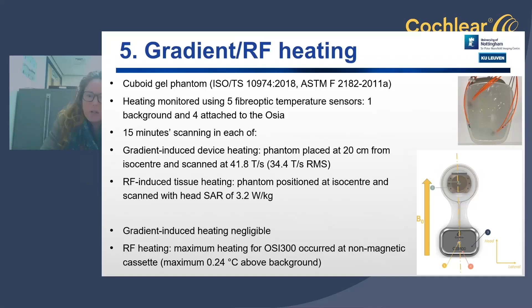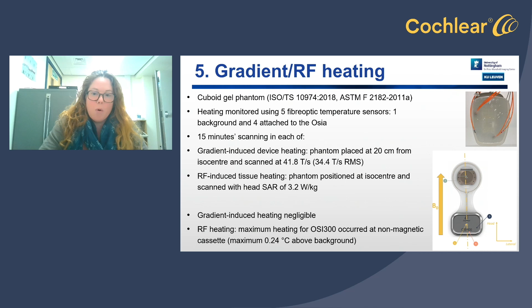To measure localized heating of the tissue around the device, we created a tissue mimicking phantom gel plus sodium chloride, into which we submerged the device with fiber optic temperature probes attached to several different locations around the device. Gradient heating was measured by scanning with a sequence set to the maximum recommended gradient strength for 15 minutes, while the phantom was placed at the worst case position of 20 centimeters from ISO center. RF heating was measured by scanning with a sequence artificially controlled at 3.2 watts per kilo, positioned at ISO center, again, because that's the worst case condition. Temperature increases reached a maximum of 0.24 degrees C above background across all probes.